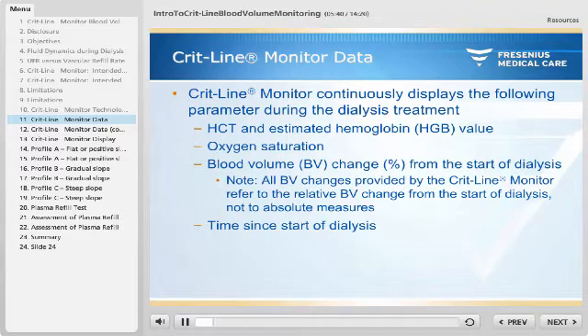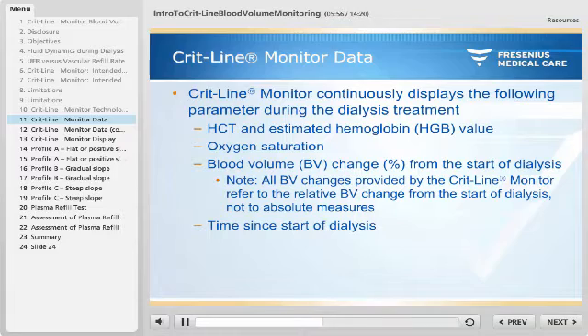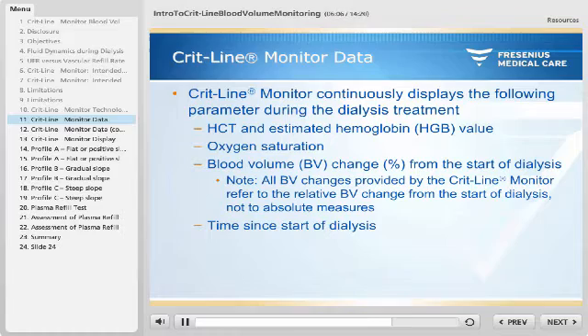The CRITLINE monitor is attached to the dialysis machine and continuously displays the following parameters during dialysis treatment: hematocrit, estimated hemoglobin value, oxygen saturation, and blood volume change in percent from the start of dialysis. All blood volume changes refer to the relative blood volume change from the start of dialysis, not to absolute measures. The monitor also shows the time elapsed since the start of dialysis.